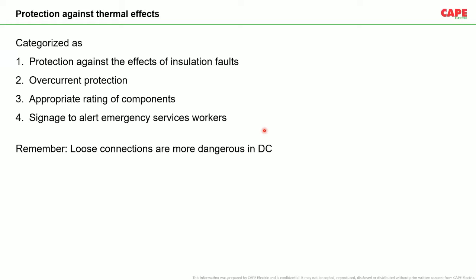Very important. Appropriate rating of the components is mandatory, because if you derate, this also leads to fire. But with derating, please understand that in an exposed area it is not only the sizing of the conductor; several other influencing factors such as sunlight, ultraviolet, chemical and mechanical must all be taken care of. The last protective measure is that you alert somebody so that they can manually do something to stop the further spread of a fire. Please remember that loose connections in DC are really dangerous.